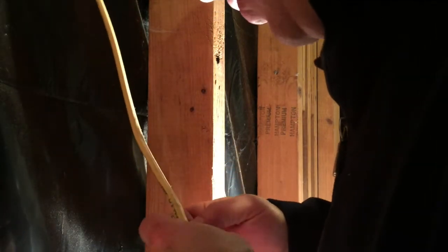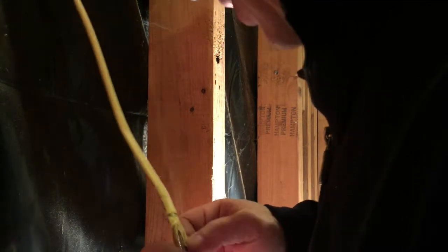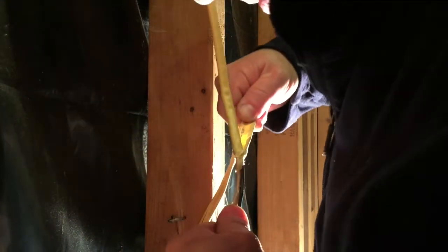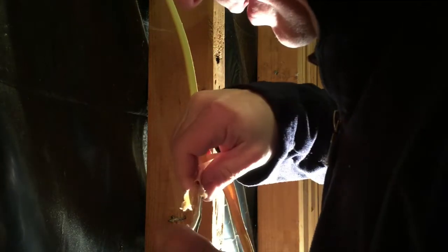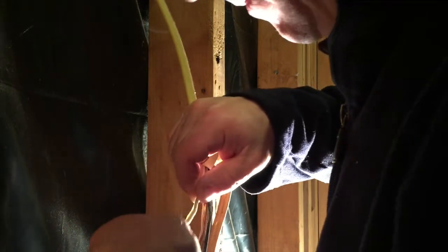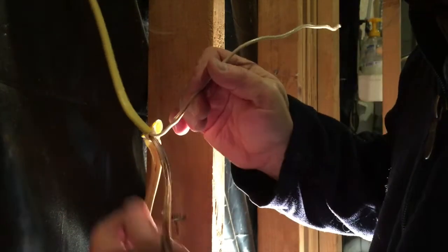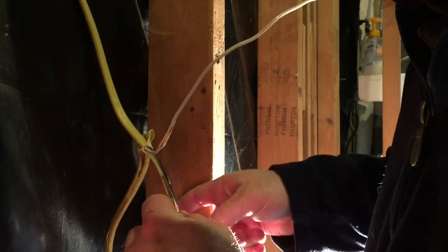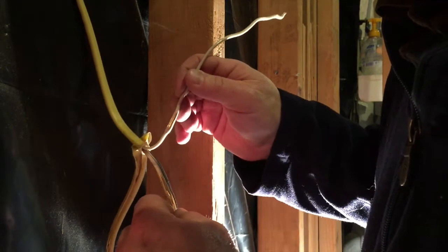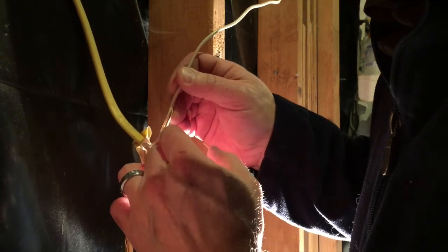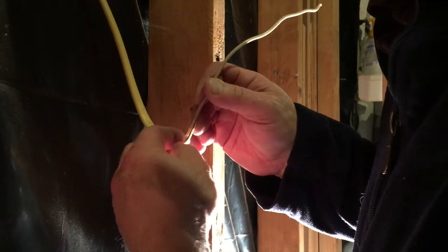Okay, that nail really crimped that jacket there. Let's see if that caused the wire to break when it got crimped with that nail. Yep, there it is, right there. That is just hitting that staple too hard, crimped that wire, and exposed the bare wire right there. And that's where my short's coming from.